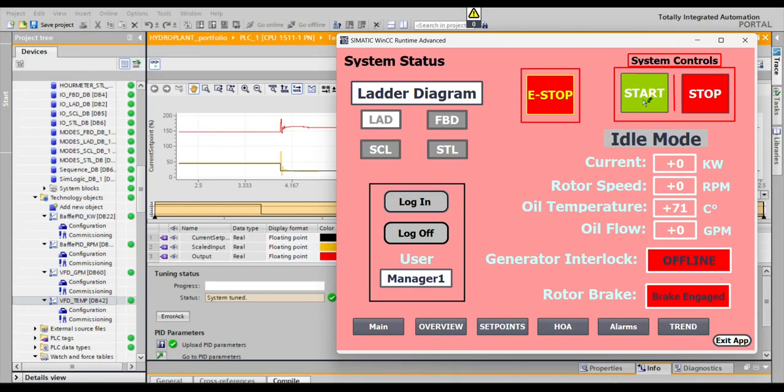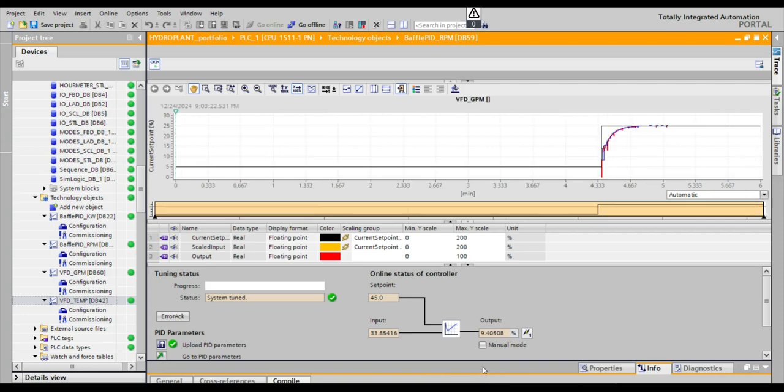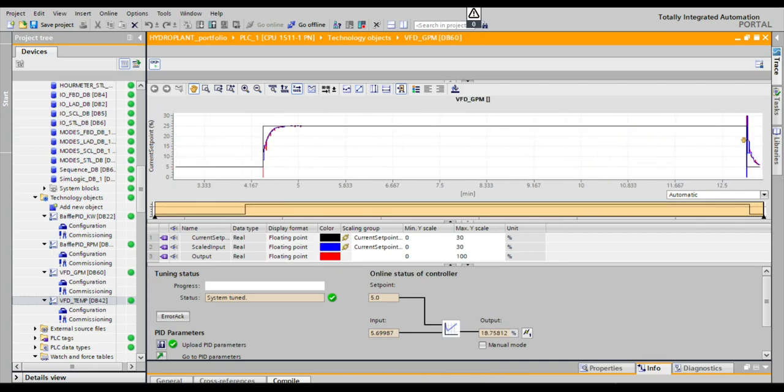Now, watching a commissioning screen, it is important to mention how the system works, and since the simulation logic is simulating a variable river flow, all the variables are going to depend on how this flow is managed, and according to the current mode, the output of the PID is going to be the percentage of the output of the device in question to control any specific parameter.